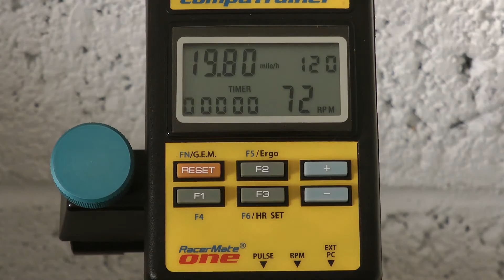So I'm now going to go back into calibration mode and recalibrate it and save that new number. You would normally ride for at least 5 minutes before doing this to allow things to warm up properly. So this is just a demo. And what I tend to do is then calibrate again after about 10 minutes, one final time. There's very rarely any change at all between 5 and 10 minutes. It's just my habit. 5 minutes is generally sufficient.